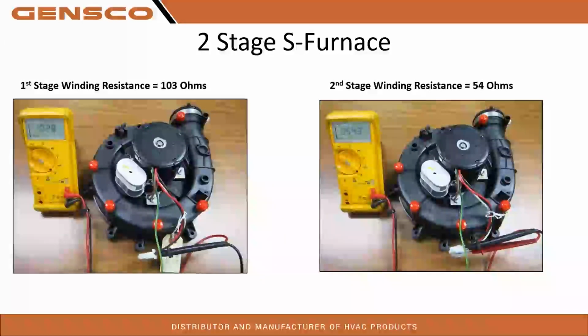Okay, two-stage S furnace. We have a PSC motor here, non-variable. So first stage winding resistance will be 103 ohms. Second stage winding resistance will be 54. We do get questions once in a while on these run caps, the 3 or the 5, I think they're 3s.